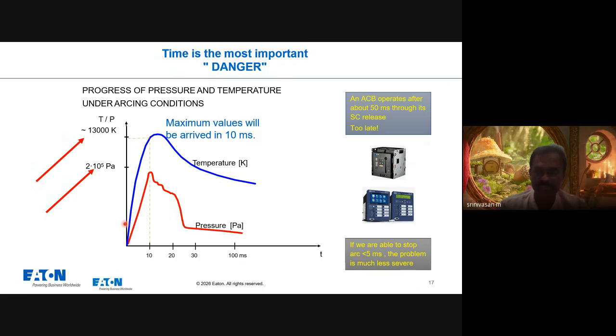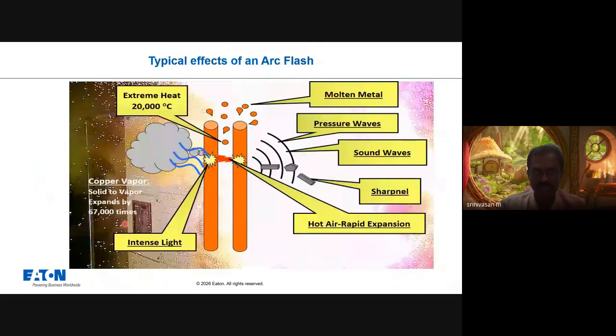That is very important. These are all the impacts happening on the internal arc switchgear: extreme heat, melting of the metal switchgear, very high pressure waves, sound waves, sharp materials being ejected, very hot air expansion, and intense light. These are all the unpleasant activities that happen when an internal arc occurs inside the switchboard.